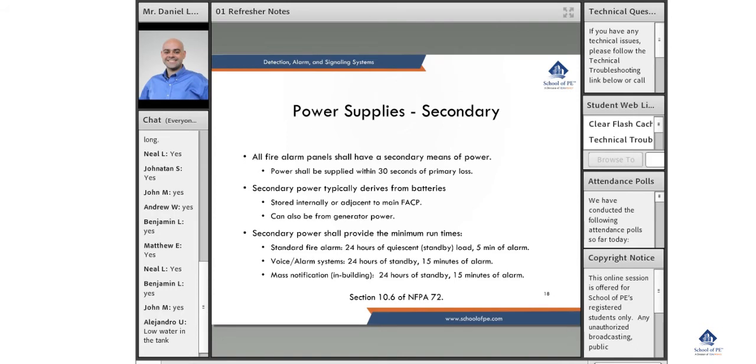All fire alarm panels must have a means for secondary power, and that power shall be supplied within 30 seconds of primary loss. It's not necessarily emergency power, which must be supplied in 10 seconds, but it is quicker than legally required power, which I believe is in 50 or 60 seconds.